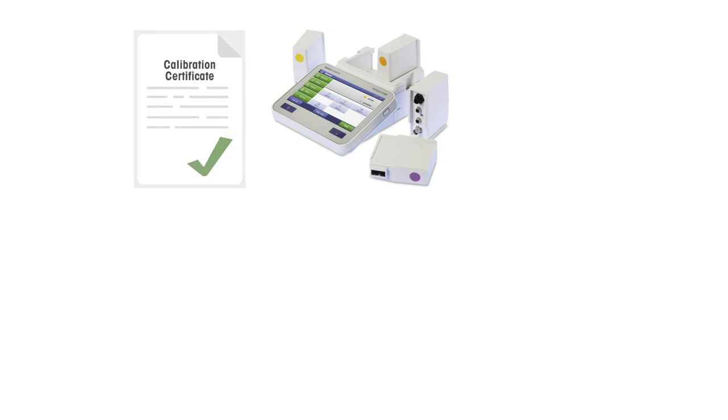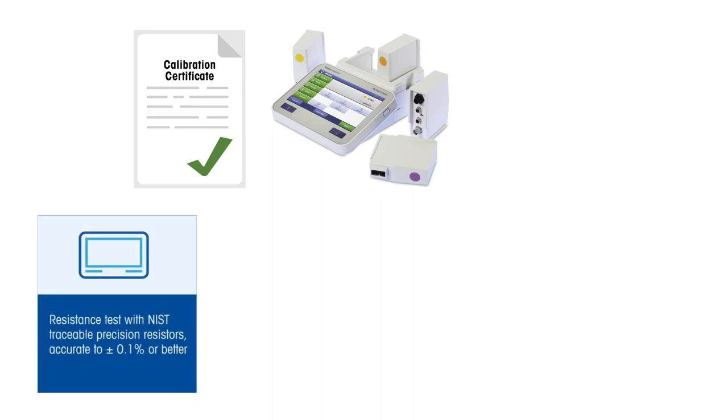USP645 defines the suitability of bulk water and sterile water samples through conductivity readings. Water conductivity must be measured accurately with calibrated instrumentation. You will require a conductivity meter whose resistance measurement has been verified with NIST traceable precision resistors, accurate to plus or minus 0.1% of the stated value.